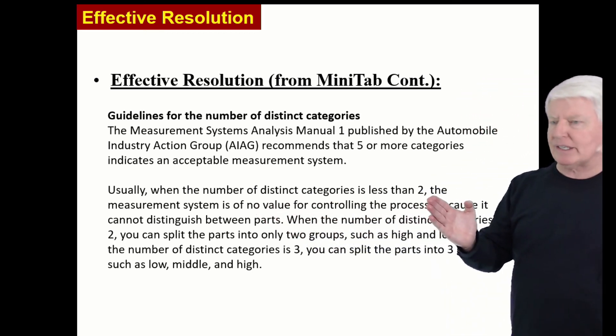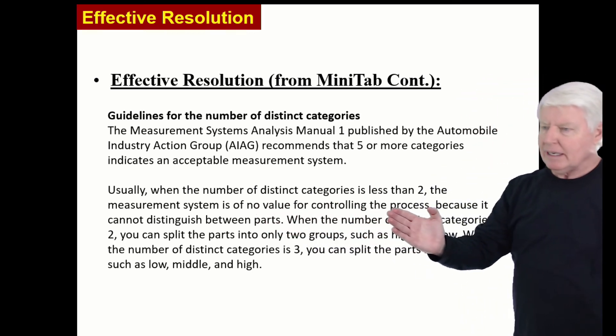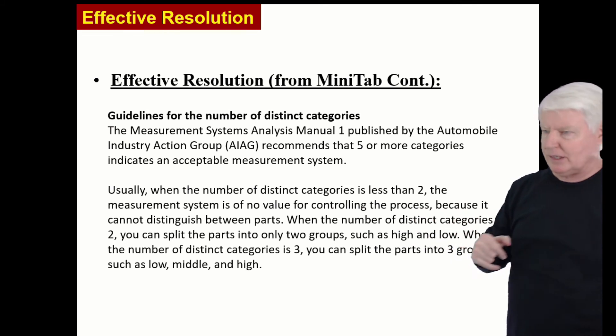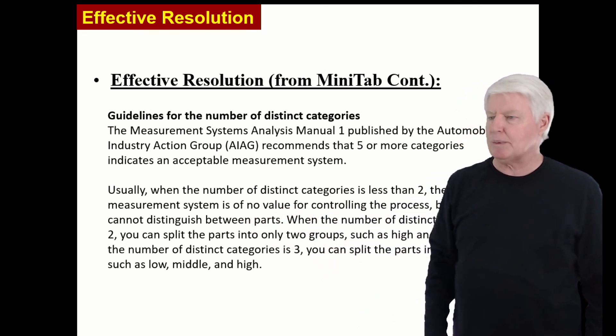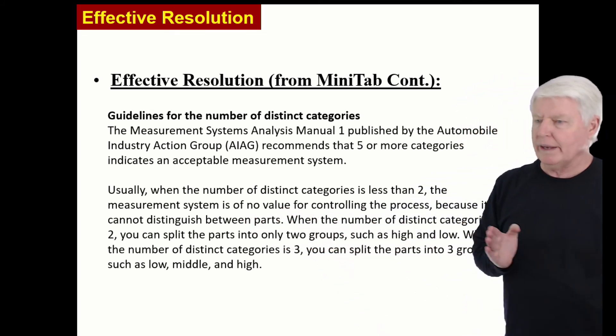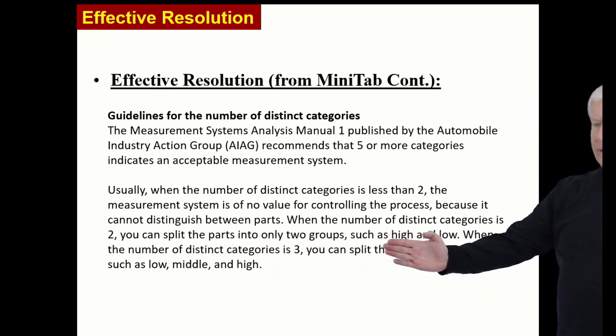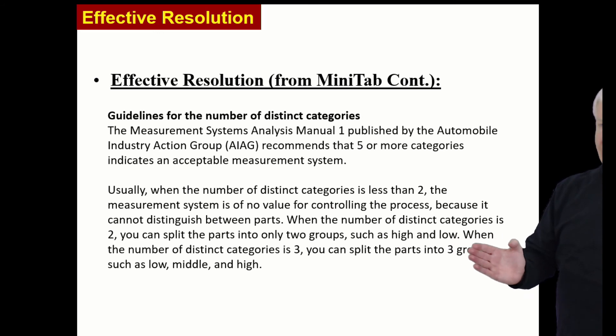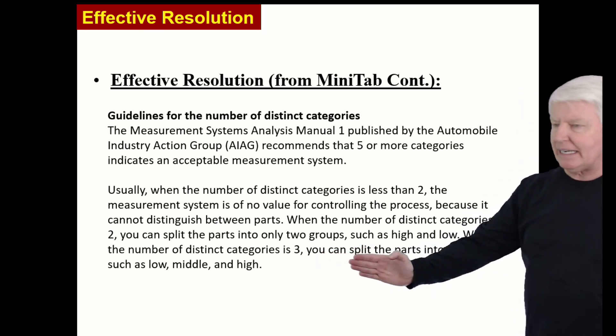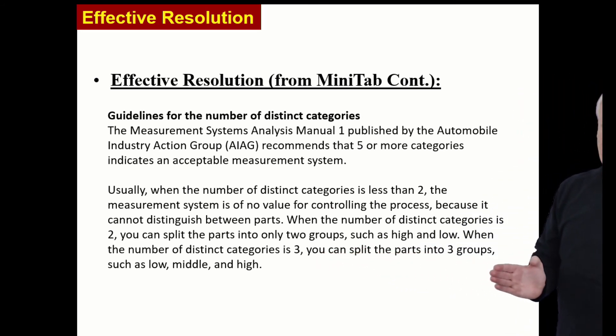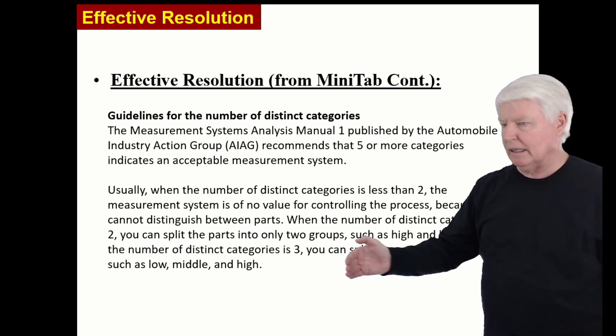Usually when the number of distinct categories is less than two, the measurement system is of no value for controlling the process because it cannot distinguish between parts. When the number of distinct categories is two, you can split the parts into only two groups, such as high and low. When the number of distinct categories is three, you can split the parts into three groups, low, middle, and high.